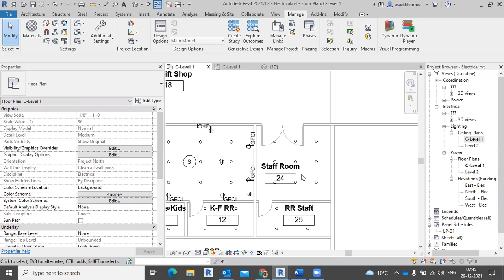Because generally the electrical department has to cover fire alarm, and the mechanical department has to cover firefighting. I mean the suppression part. We cover the detection and annunciation part, and they have to cover the suppression part. So sprinkler, piping, all those things they will cover. Fire hose cabinet, yeah. So if you are only covering electrical, then that will not come into your part. So coordination needs to be there. Whatever you have put as lighting, they have to make sure it is coordinated.